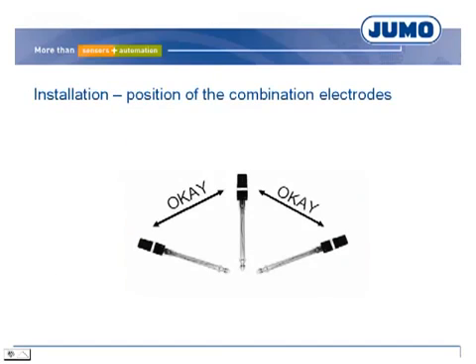It is important that the membrane and diaphragm are completely covered by the medium. Furthermore, the electrical connection has to be above the glass membrane. A position of at least about 10 degrees from the horizontal is advised.